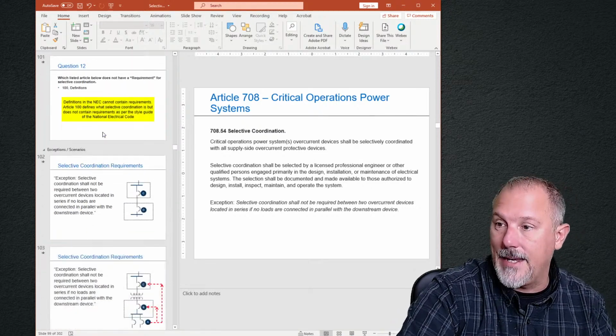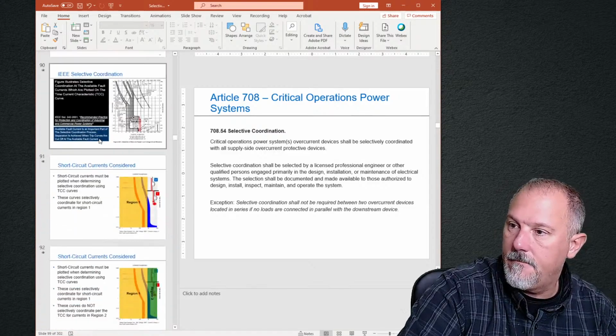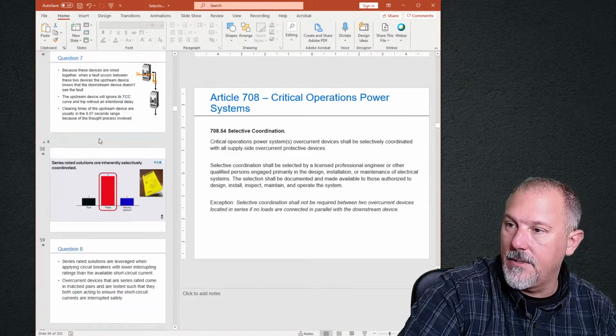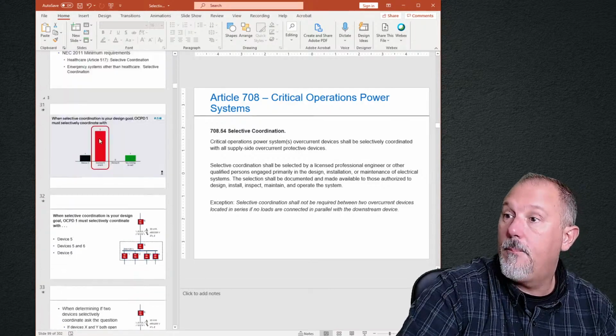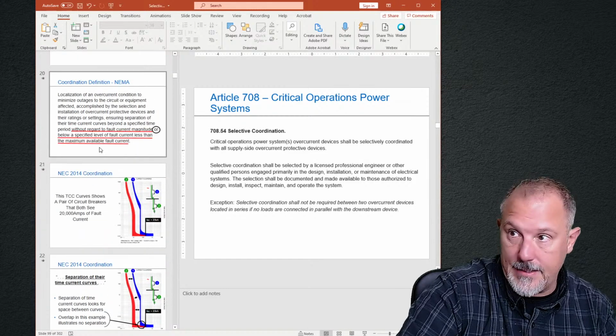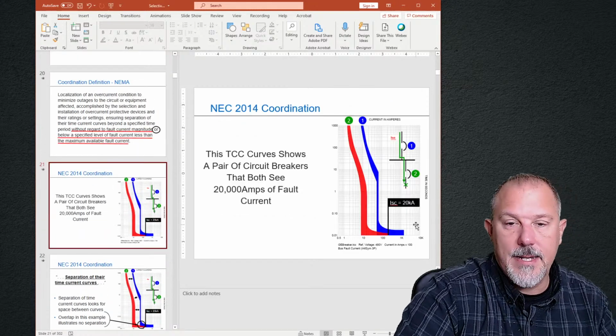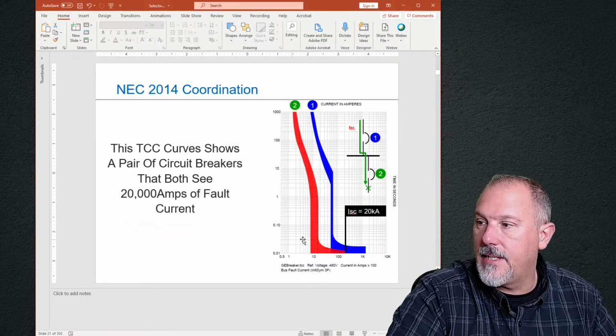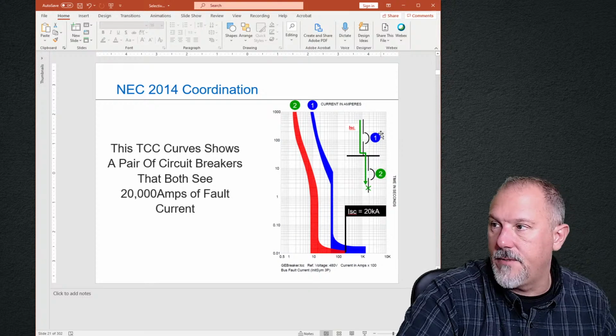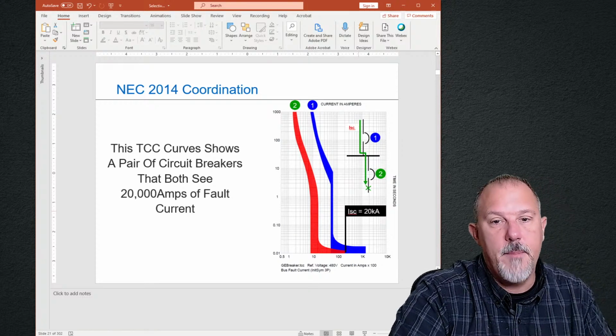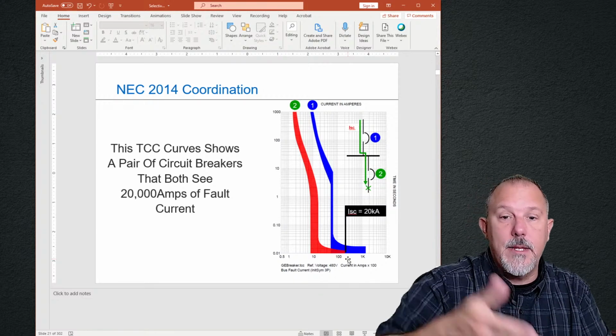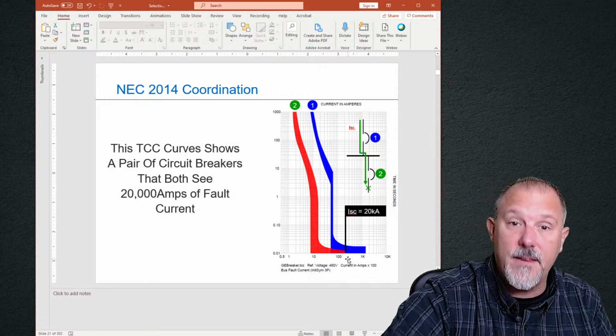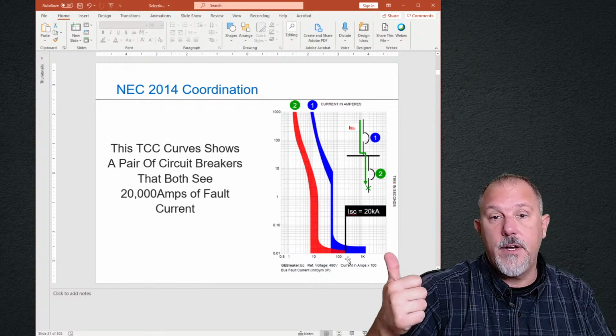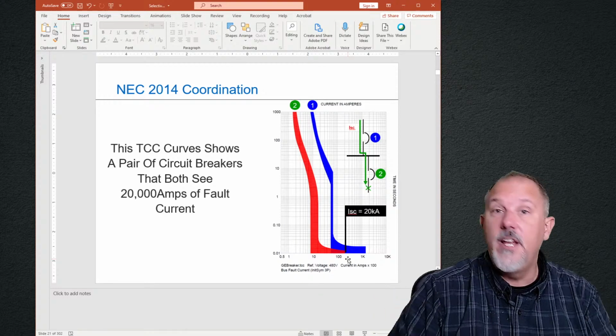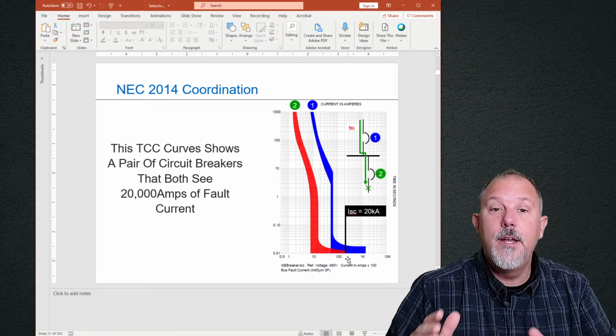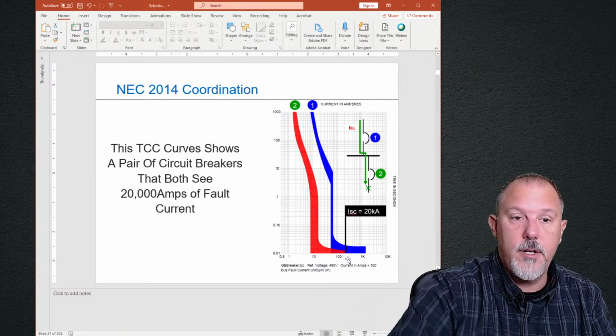What you do for 0.1 seconds, and I might have some slides in here that cover 0.1 seconds. 0.1 seconds makes your life easy. So here we go. There's 0.1 seconds. So let's talk about what it does. If I have these two breakers, an upstream breaker and a downstream breaker, and my available fault current is 20,000 amps, I know I am well into the instantaneous region. I know for a fact they will both open on that bolted fault current value, or if that's the ground fault current value, I don't care. If it's the arcing fault current value, I don't care. I know for 20,000 amps, they're both going to open.